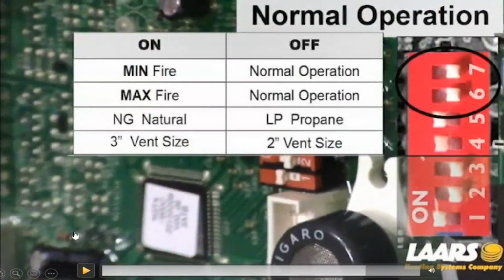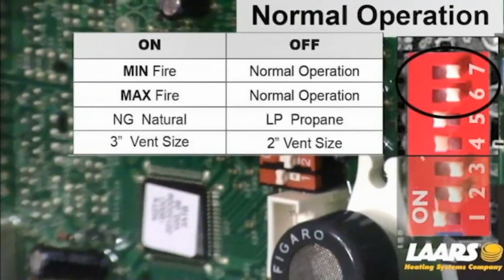Now, if you forget to put your dip switches back, that boiler will stay in that mode. So if dip switch 6 was in the on position, that's high fire. Every time it lit off, it would modulate right to high fire, and you would start short cycling your boiler. If you left dip switch 7 in the on position, that's low fire.